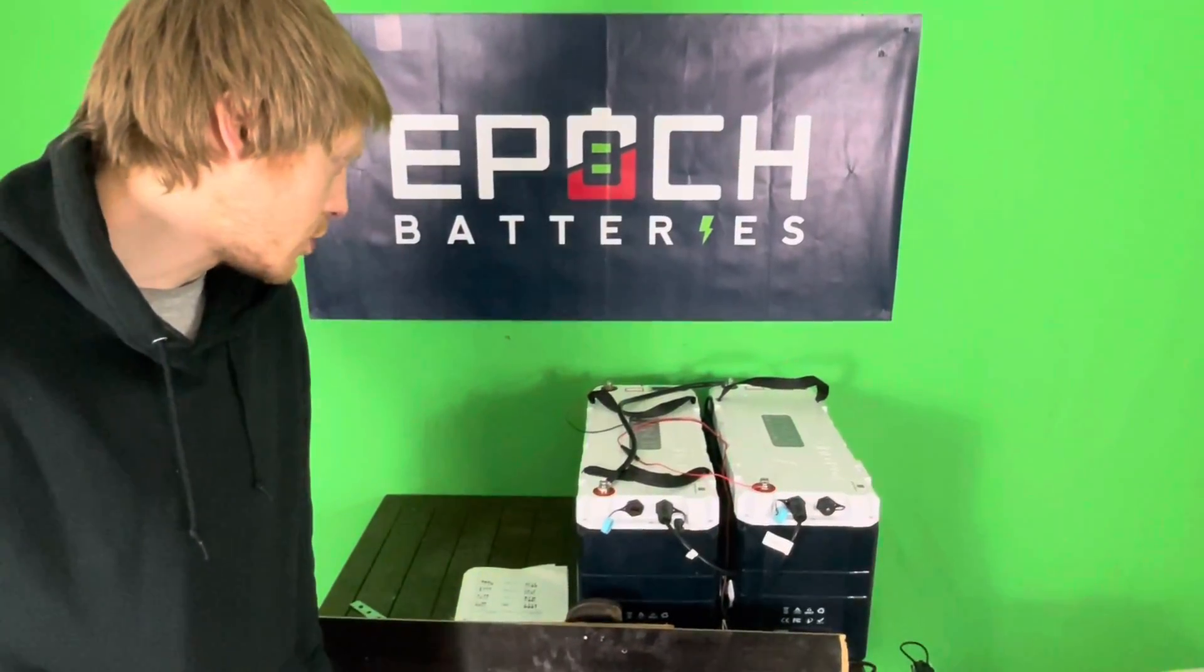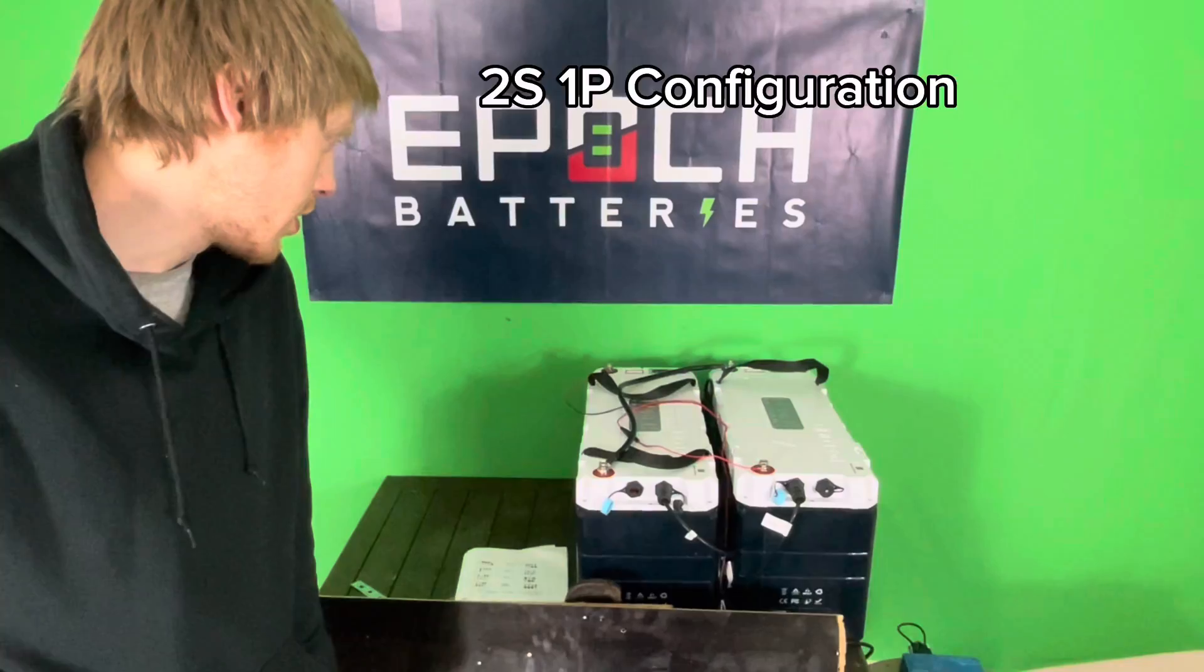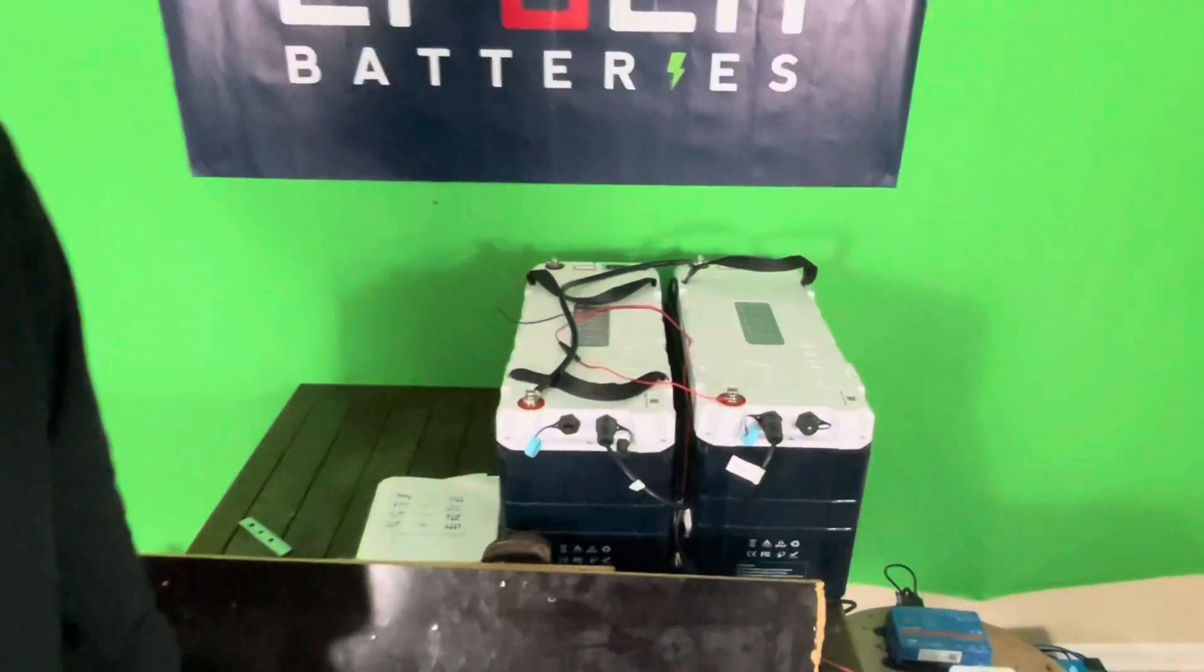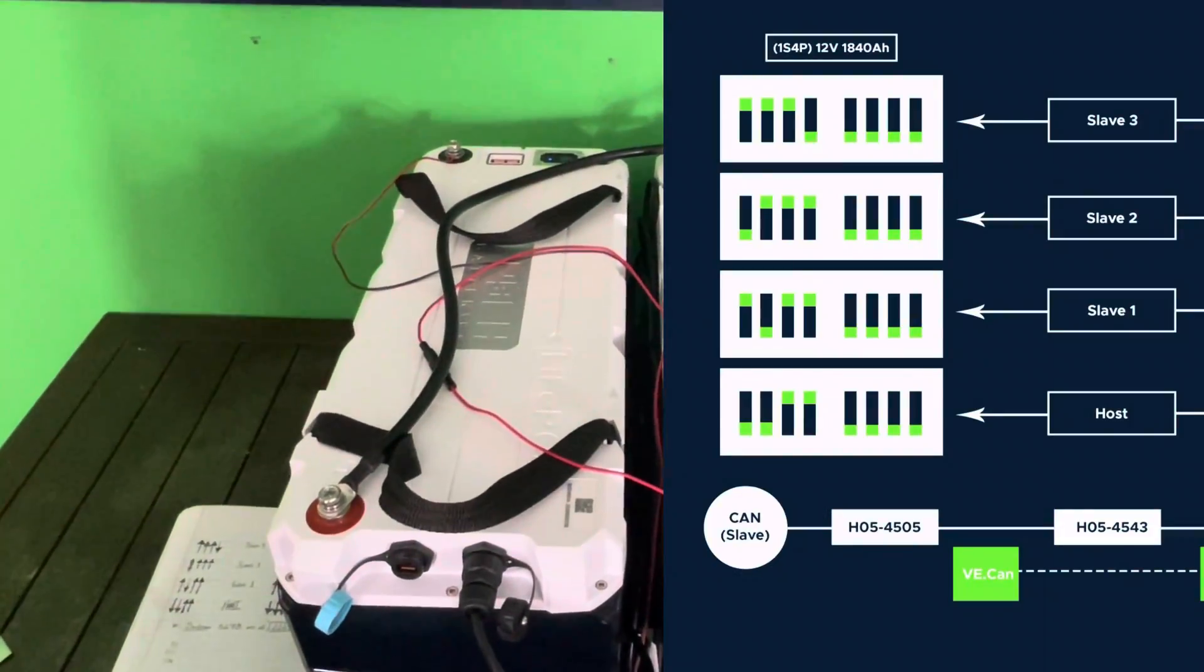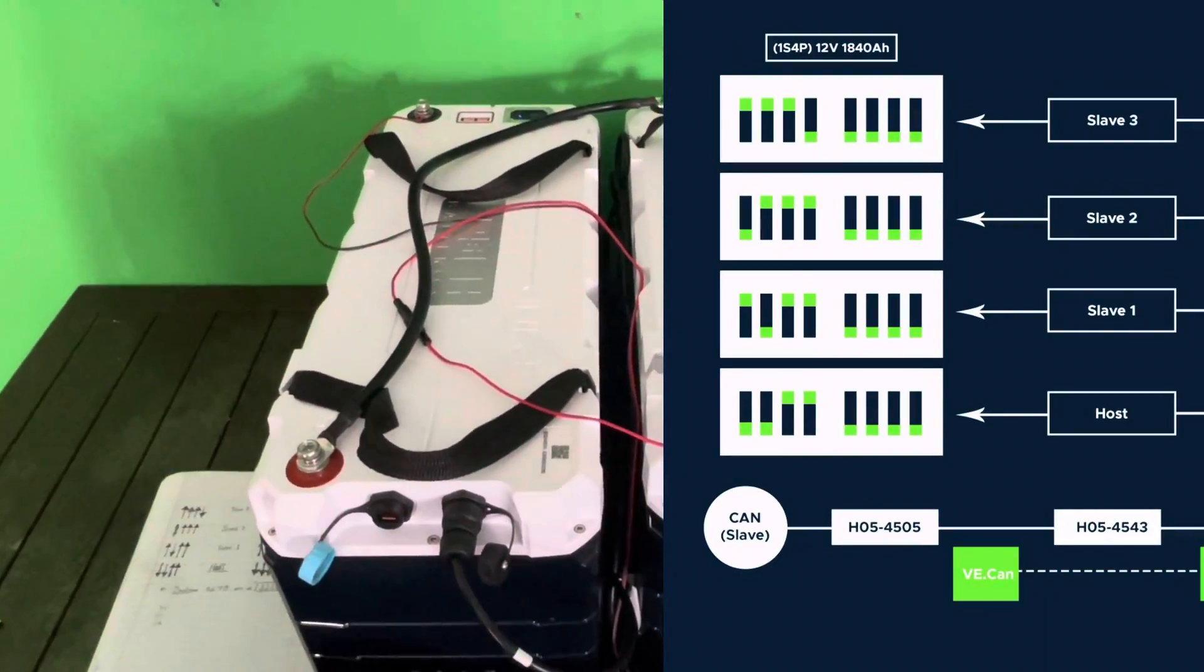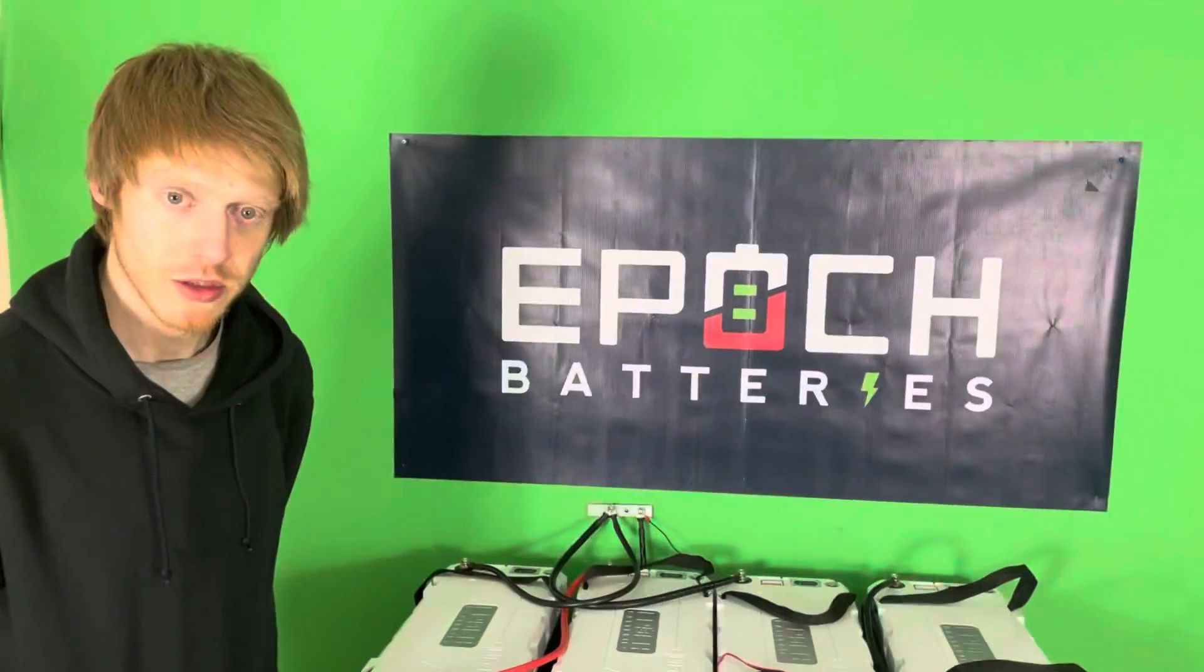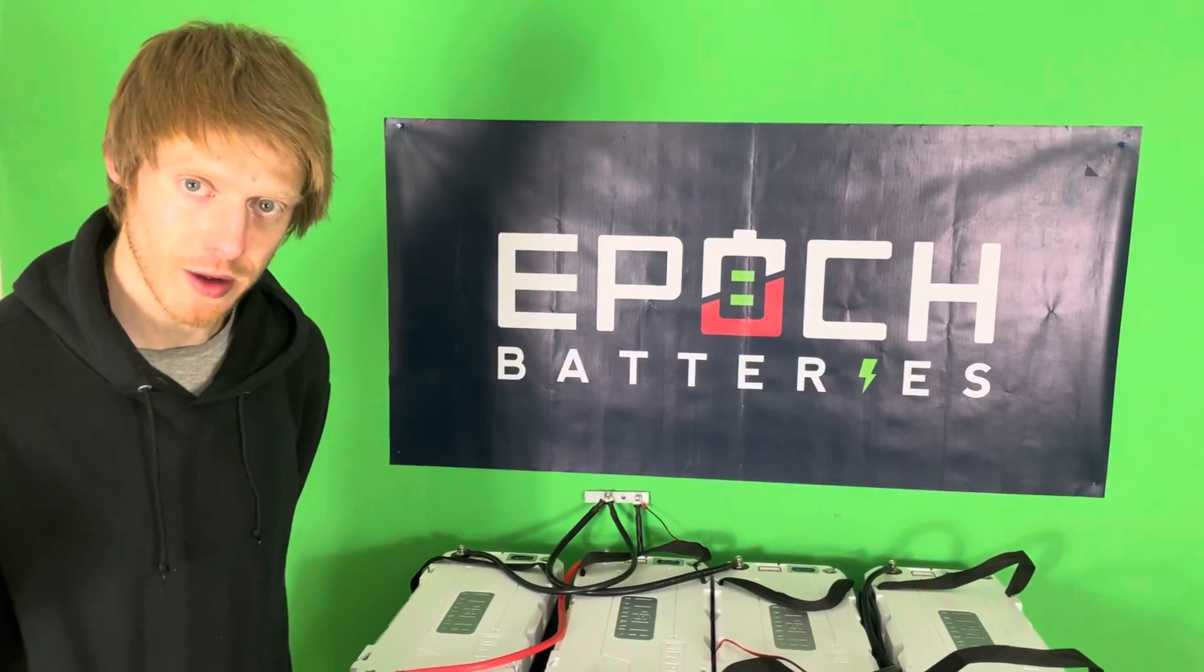Alright, so now for the 2S1P configuration. So we have a 24-volt battery, 460 amp-hour, wired in series. Dip switch settings as seen on the screen, and that's seen on the Cerbo and we have the 24-volt battery. So that's all for this configuration and now on to the next.